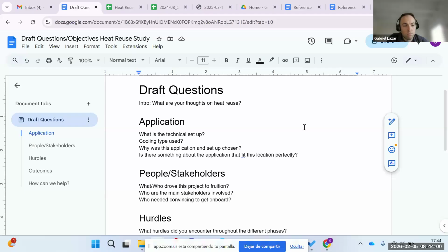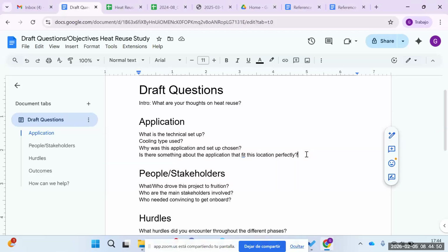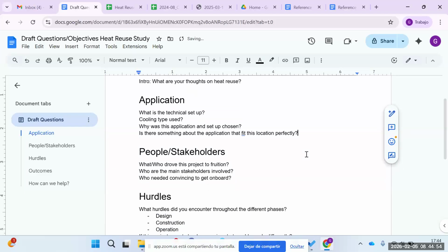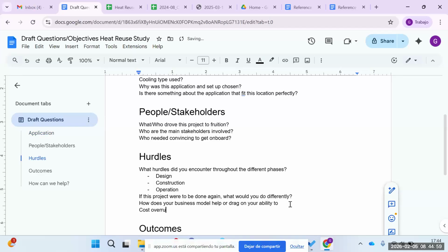The other thing is somebody asked, is air going away? Air is never going to go away because we still have transformers, PDUs, and storage systems that don't have a cold plate on them. So unless you put a cold plate or tubing through transformers and PDUs and everything else, then maybe you have a full liquid cool facility, but you're always going to have CRAC units, fan cool units, air handling units. There's a balance in figuring out whether you pick up the primary side, which is a blend of technical water systems doing liquid to chip, and the balance of air-cooled systems bringing that heat back with coils. So if each site has a unique primary chilled water system or primary condenser water system, those temperatures need to be understood to figure out how you can reject that heat to a local consumer or off-taker. Just want to throw those two in there because they have a major influence on how you move forward.